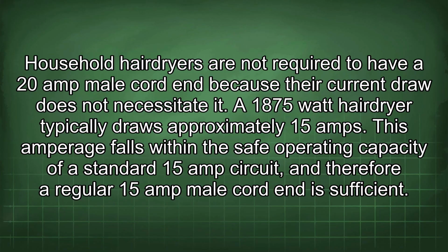Household hairdryers are not required to have a 20 amp male cord end because their current draw does not necessitate it. A 1875 watt hairdryer typically draws approximately 15 amps. This amperage falls within the safe operating capacity of a standard 15 amp circuit, and therefore a regular 15 amp male cord end is sufficient.